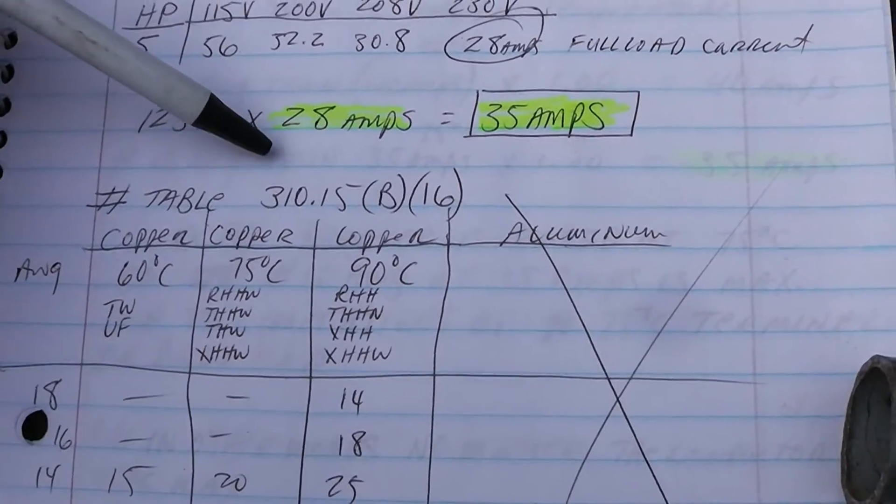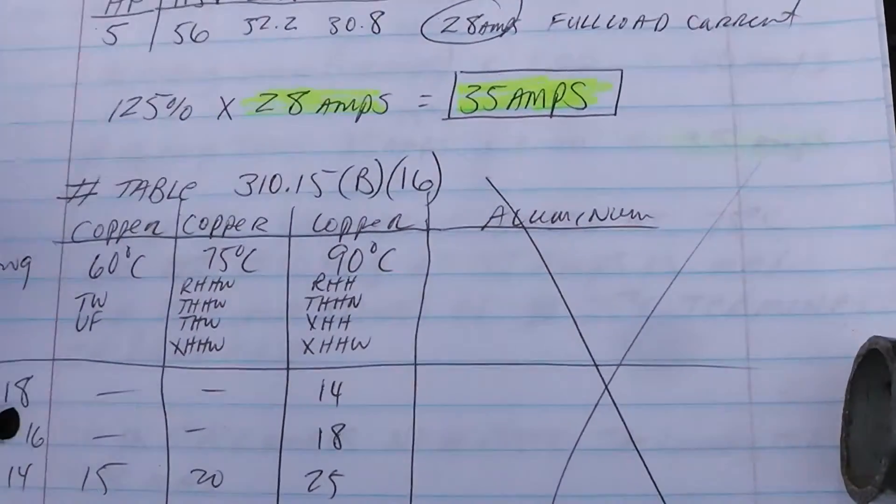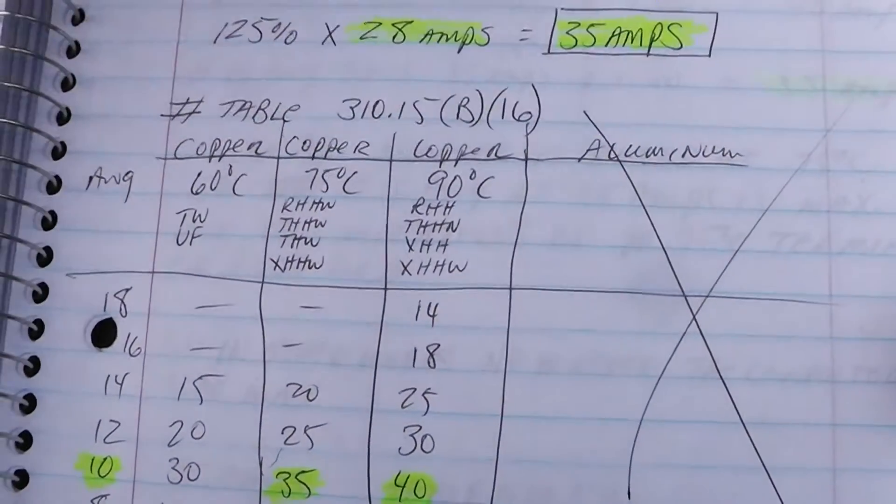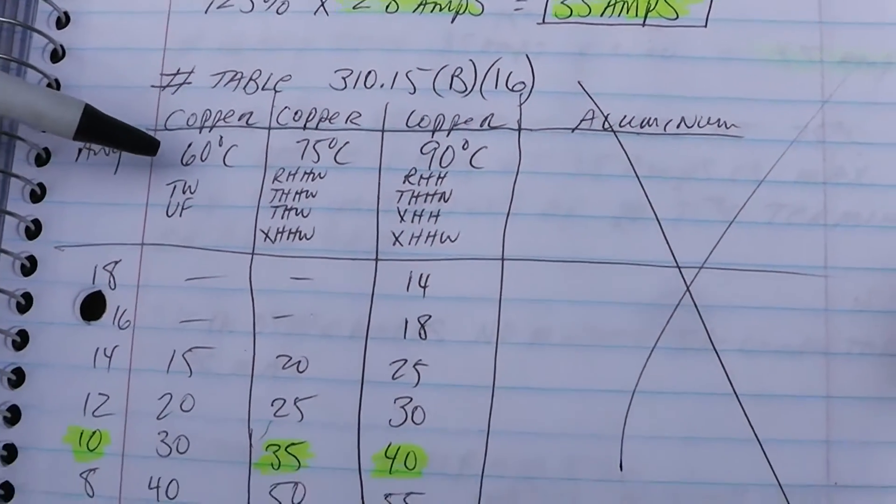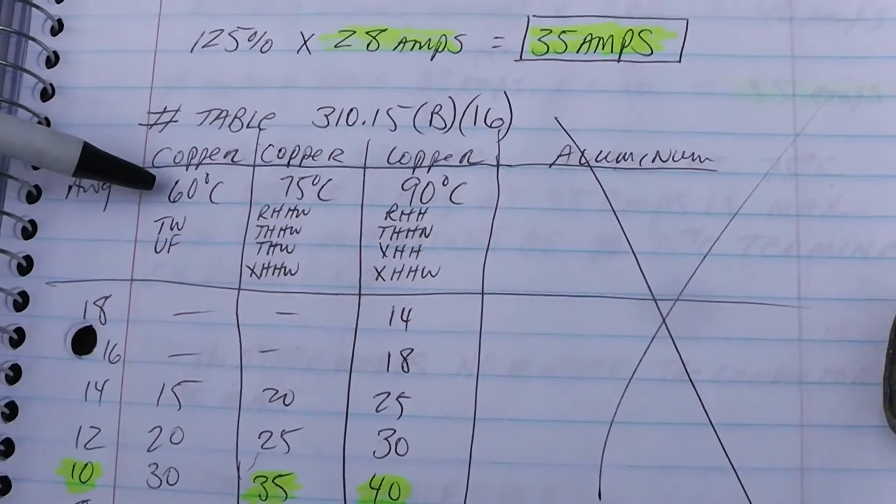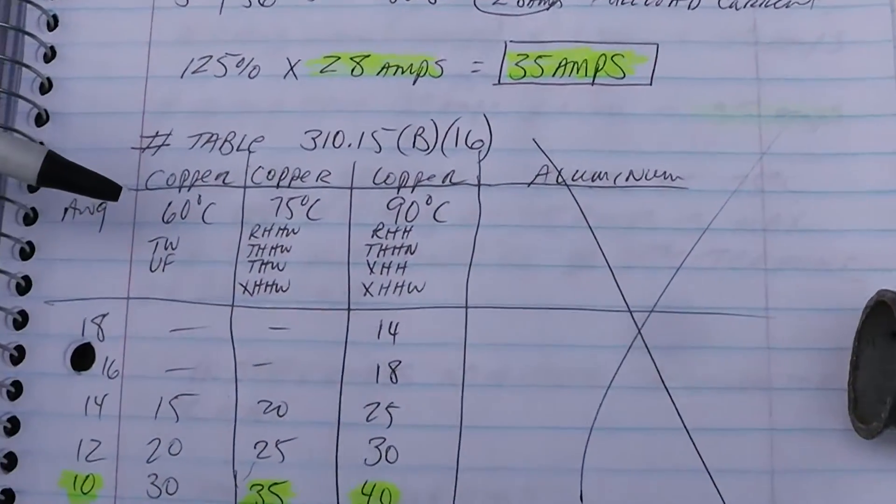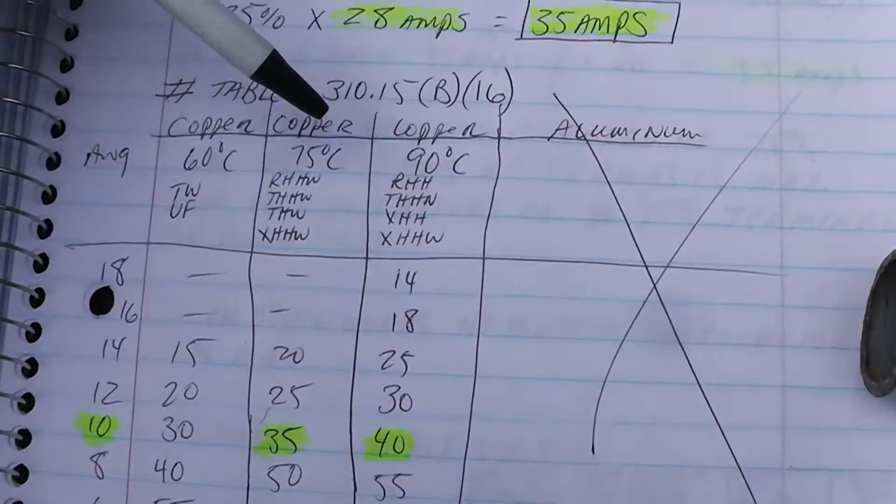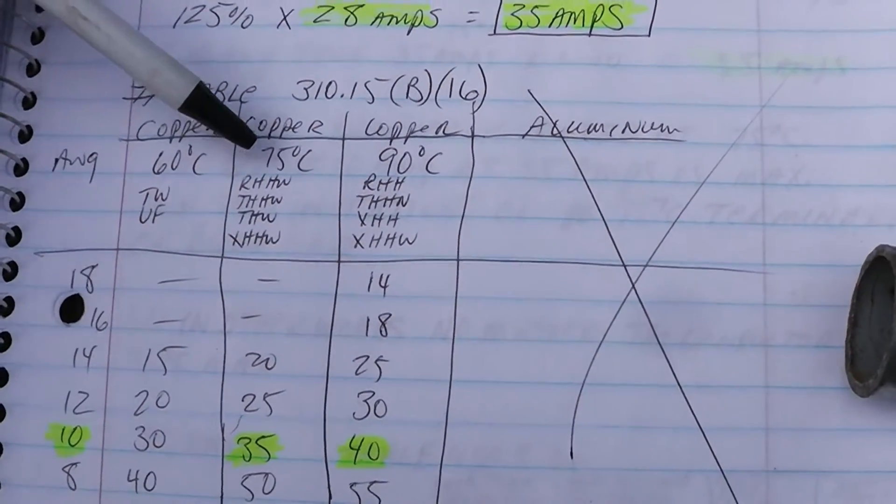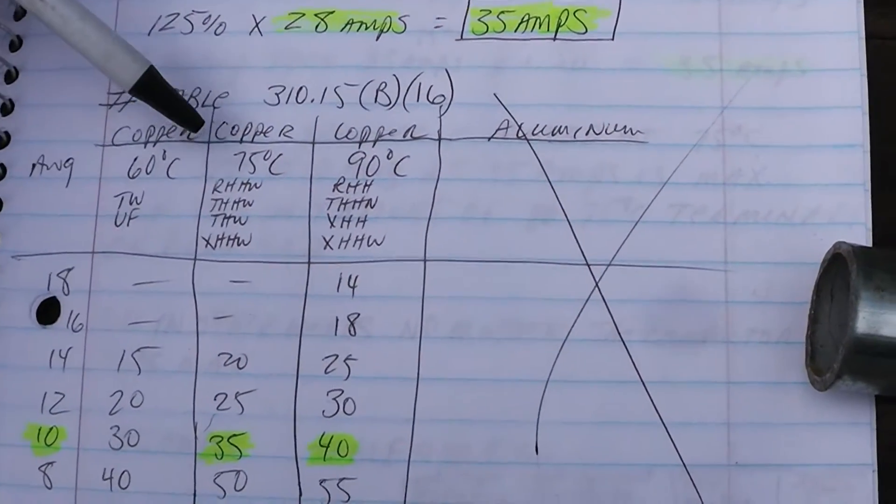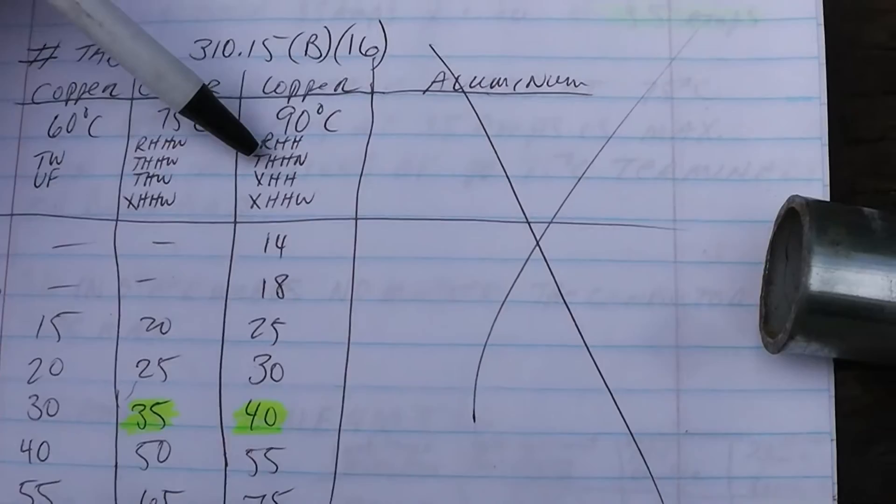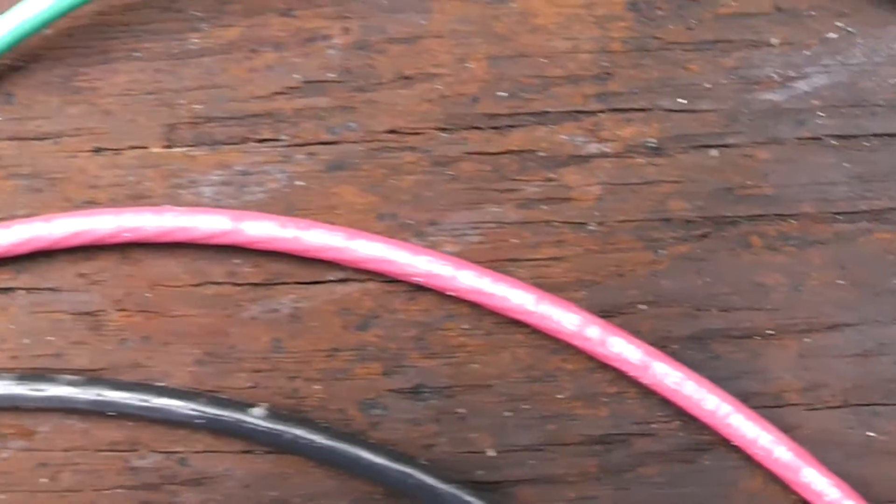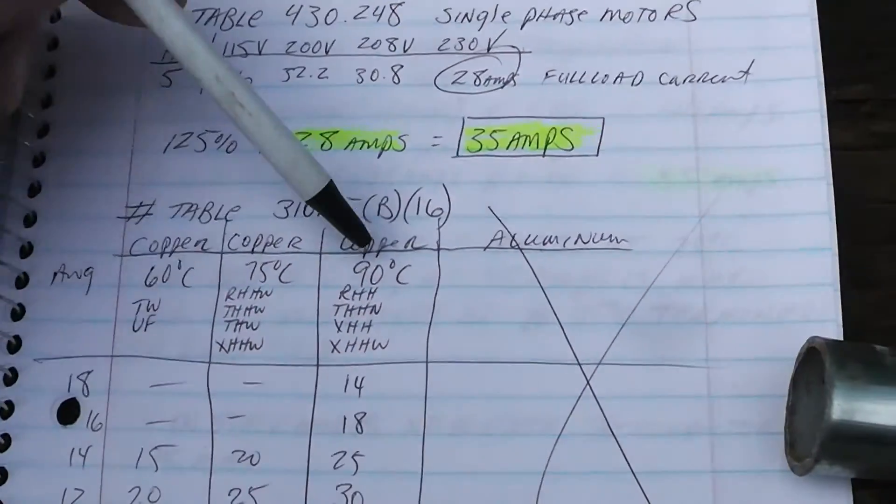How do we figure what size wire we need? If you go in the National Electric Code book 310.15b16, you'll see a table with copper on one side and aluminum on the other. I'm not going to use aluminum. You're not protecting the wire, you're protecting the insulation on the wire - the wire is going to take a whole lot more amperage than these tables have. We go by the temperature rating that the insulation is on the wire.